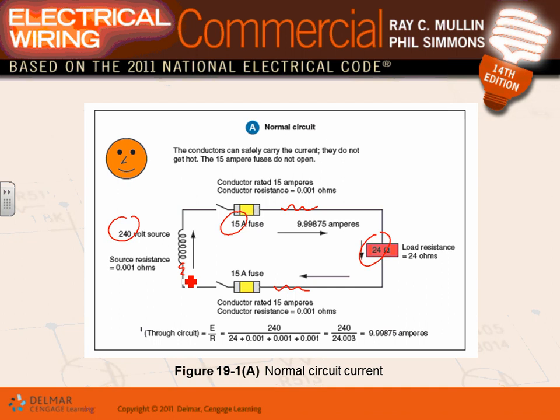So when you do your math, guys, you take the voltage divided by the resistance, it gives you close to 10 amps. So you have a light burning at 10 amps, a big light, or I don't know, a microwave burning 10 amps, and at 240, the voltage of that baby is 240, you can see. The fuse is 15 amp. This circuit is normal operation condition of a circuit. It can run forever, right? Look at that, 10 amp load here. I have 10 amps load coming out of 15 amp. It can run forever. That's your normal operation condition.